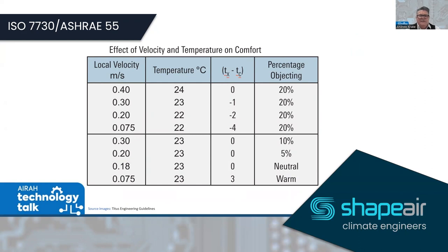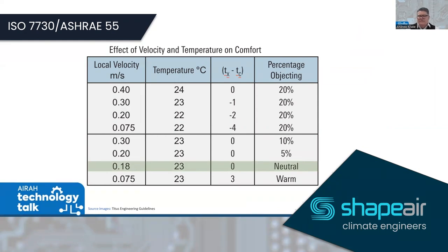With a velocity of 0.4 m/s within the space and a temperature of 24°C, 20% of people would be dissatisfied — purely from air velocity being too high. Reducing to 0.3 m/s at 23°C brings dissatisfaction to about 10%. At 0.18 m/s and on temperature, virtually everybody in the space would feel a neutral effect — no one would be feeling cool or warm.